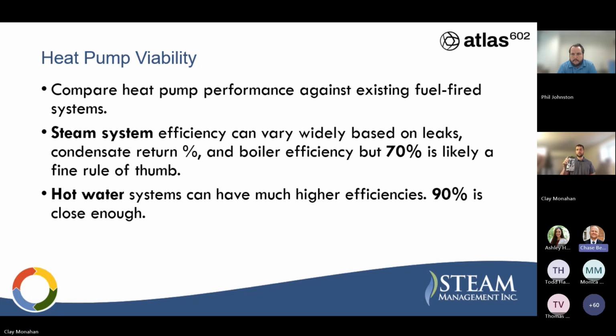Somebody asked what was the 50% estimate in the previous slide? Is that a system-wide efficiency? Yeah. So if we look at a refrigerant based heat pump, and you're lifting from that 110 to 160 degrees, it's going to have oil cooling the system, and that oil needs to be cooled. That's one example of losses. It's going to have various points in the system where it's losing thermodynamic efficiency. So if you do the temperature calculation and the theoreticals, 8 as a COP, let's say, you're only going to be able to achieve 4 from that because of the heat you have to reject from losses in the system. That's through the drivetrain, that's mechanical. Yeah, pump efficiency, casing losses, thermal losses, all that.